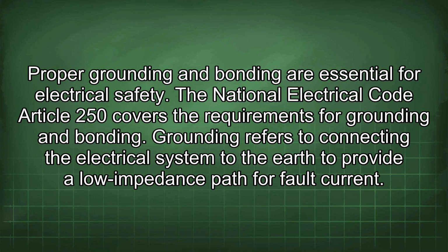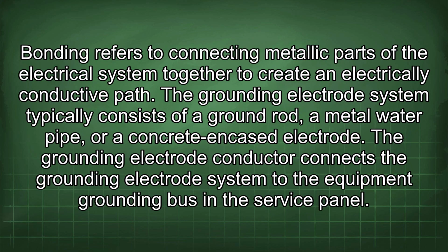The National Electrical Code Article 250 covers the requirements for grounding and bonding. Grounding refers to connecting the electrical system to the earth to provide a low-impedance path for fault current. Bonding refers to connecting metallic parts of the electrical system together to create an electrically conductive path. The grounding electrode system typically consists of a ground rod, a metal water pipe, or a concrete-encased electrode. The grounding electrode conductor connects the grounding electrode system to the equipment grounding bus in the service panel.